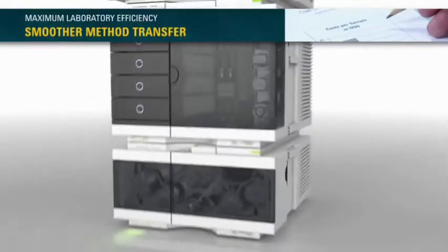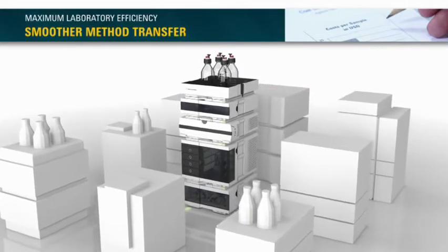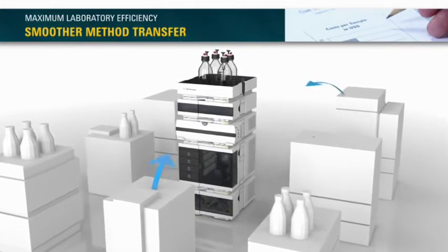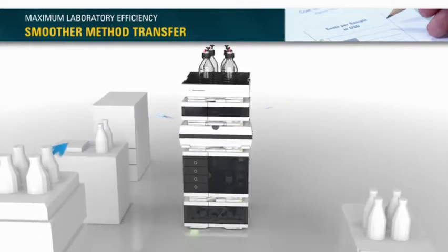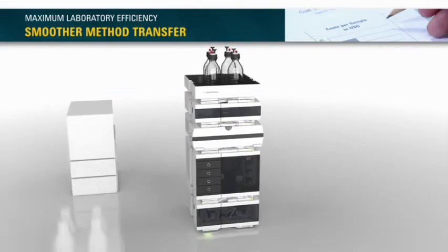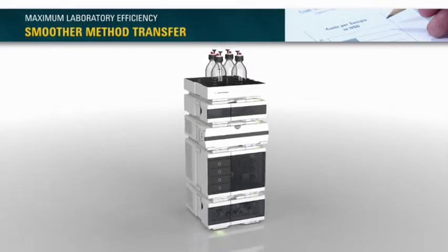Intelligent system emulation technology executes any HPLC or UHPLC method while delivering the same chromatographic results. That means smoother method transfer between any instrument, regardless of brand. You can phase out your legacy LC systems while keeping your valuable methods.